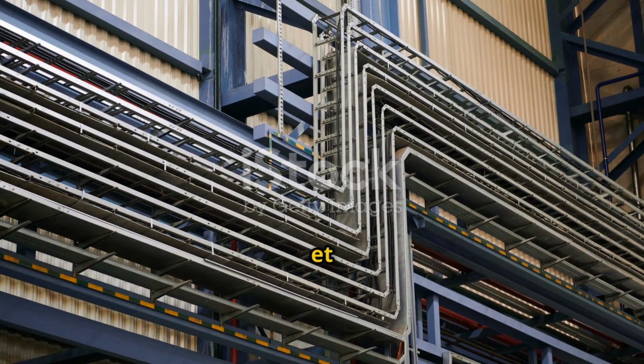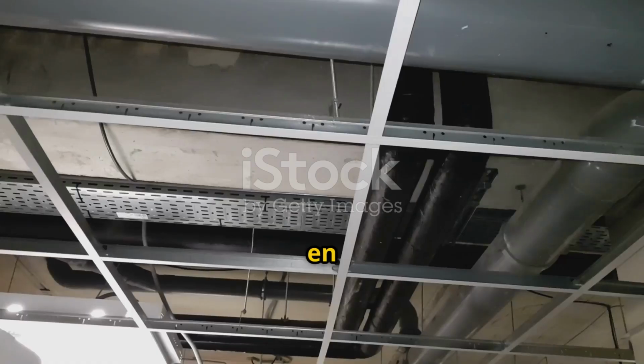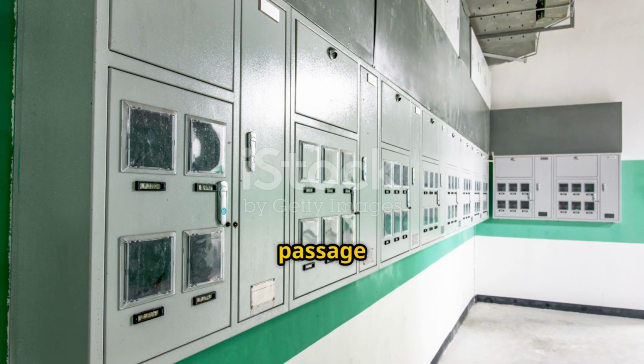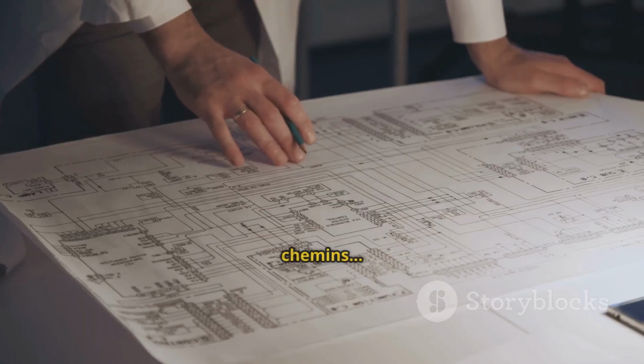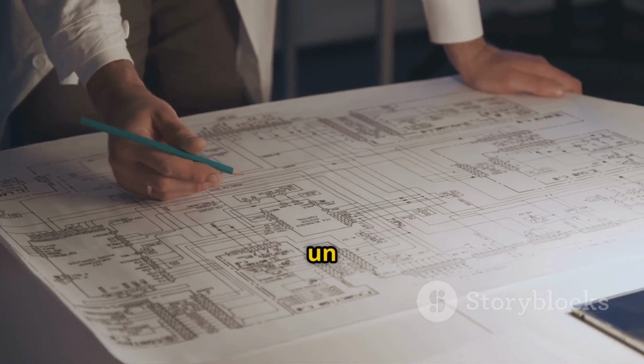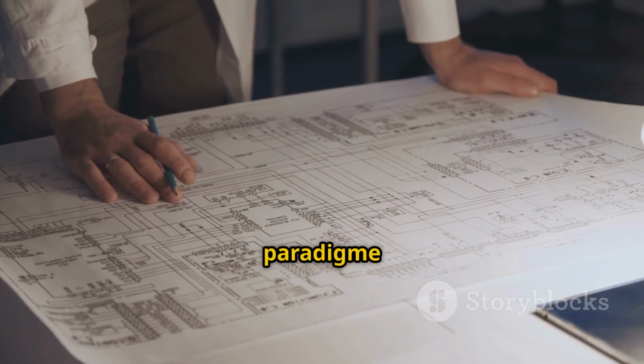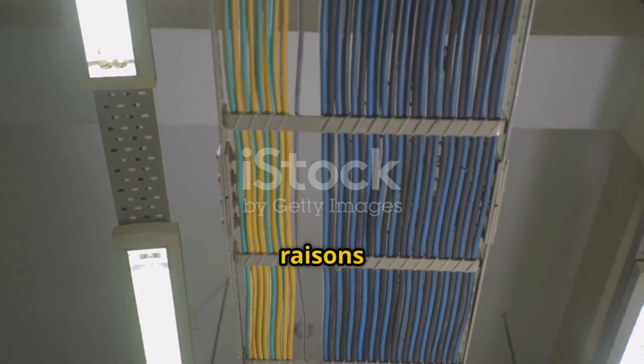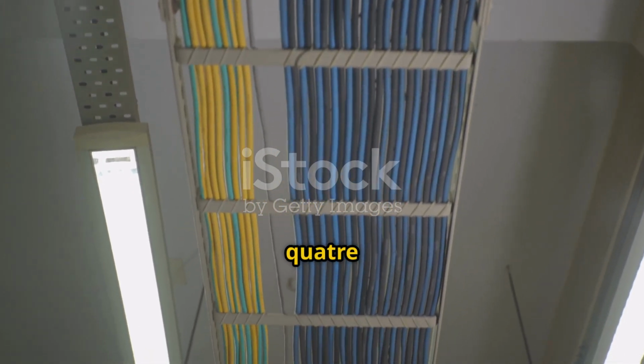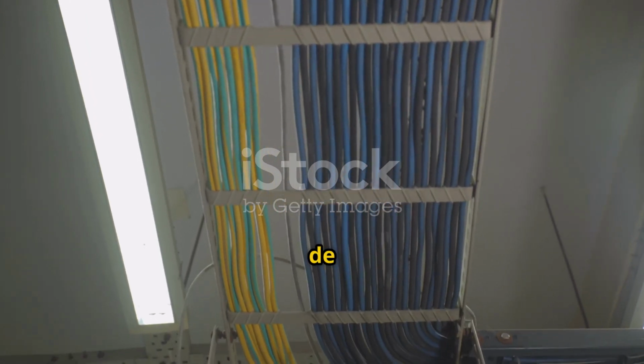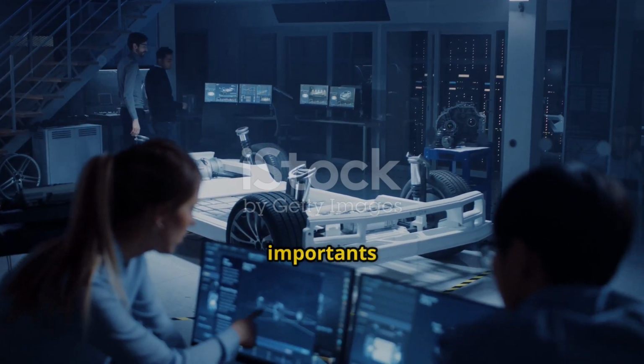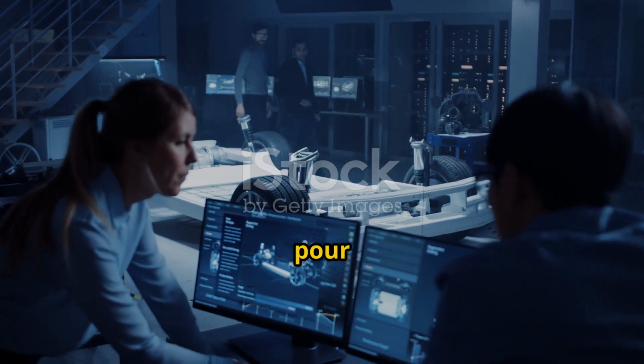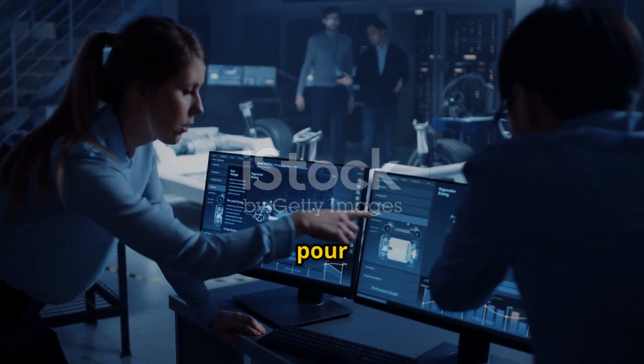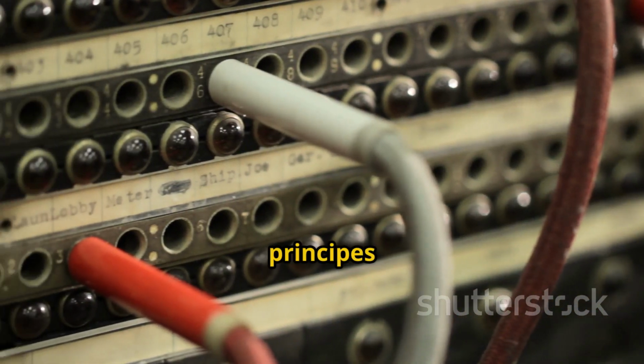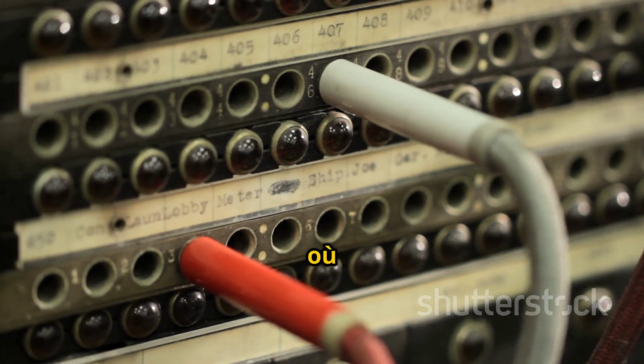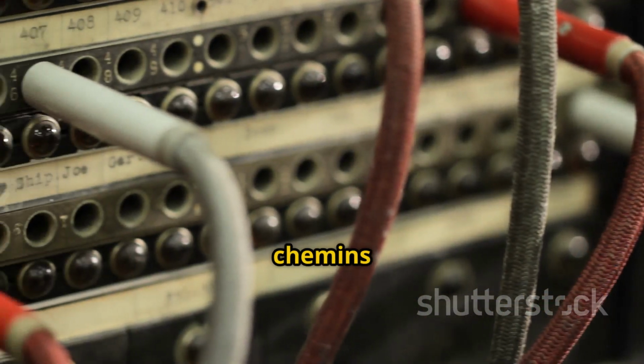The shift from individual conduits to open cable tray systems was not just a minor change, it was a paradigm shift in electrical engineering. The reasons for this shift are rooted in 4 key advantages: safety, cost-effectiveness, flexibility, ease of maintenance. These benefits are so significant, they've made cable trays the standard for industrial and large commercial projects worldwide. Understanding why they matter is to understand core principles of modern electrical design, where efficiency and safety are paramount. The adoption of cable trays resolved many critical flaws in older wiring methods, paving the way for larger and more complex installations than ever before.